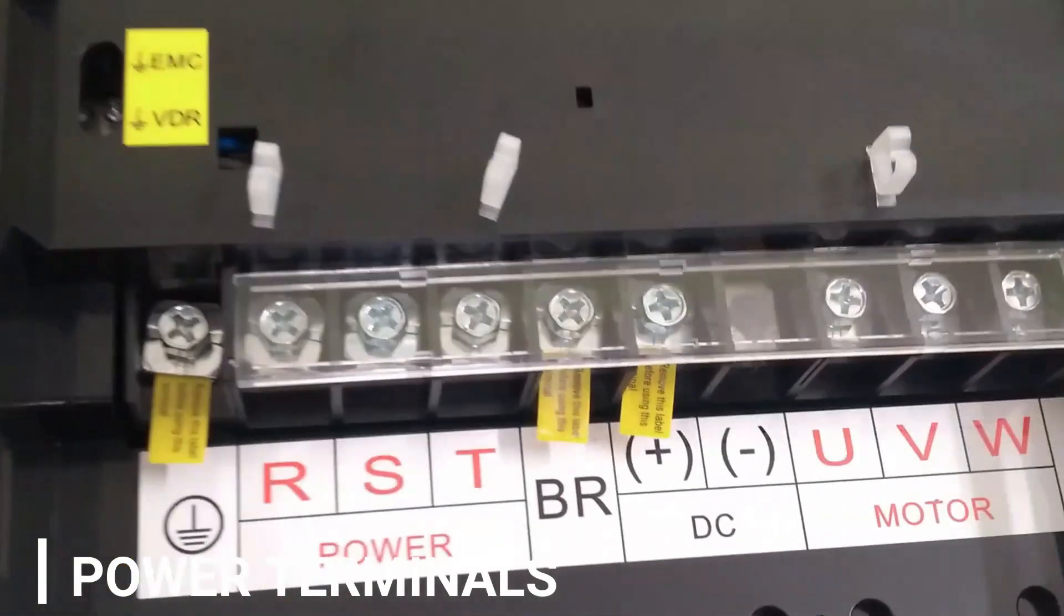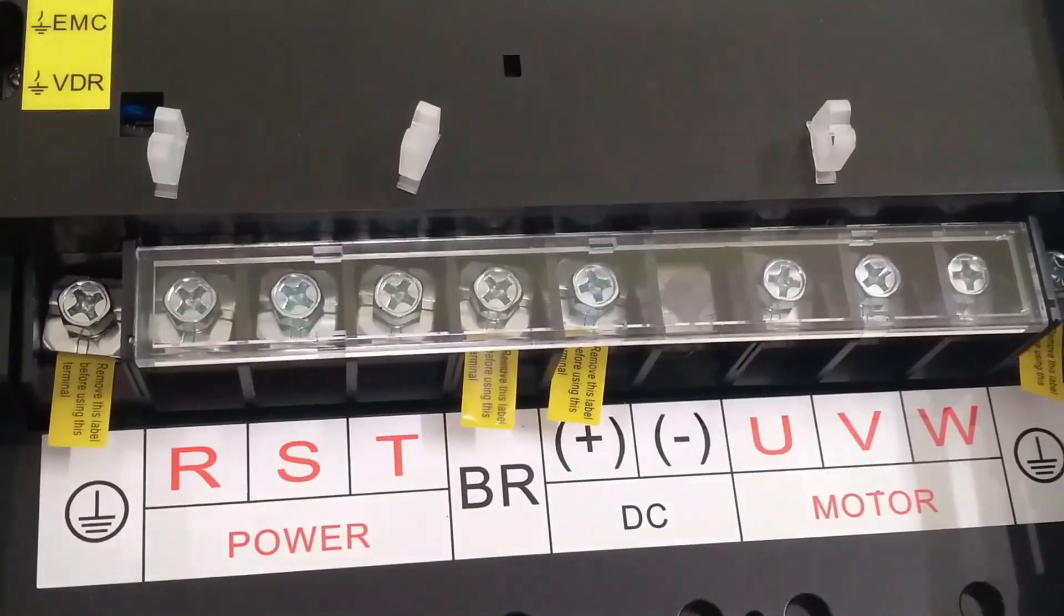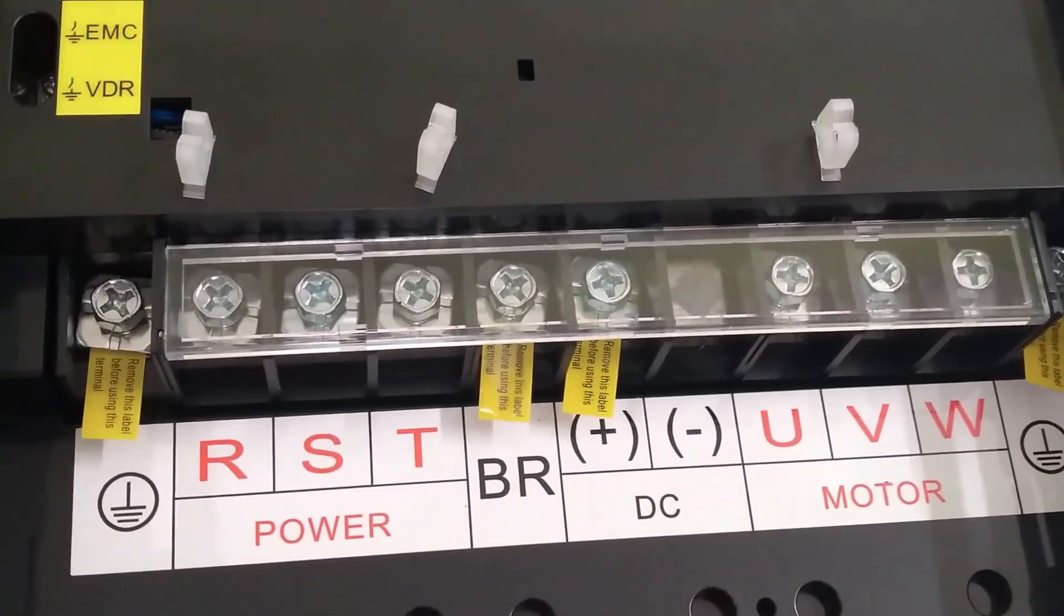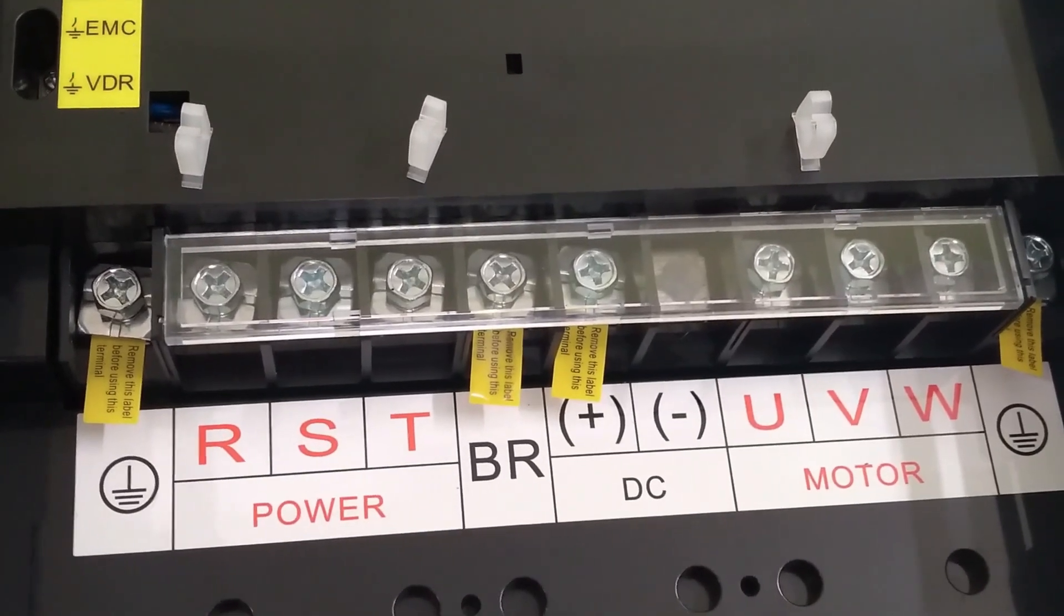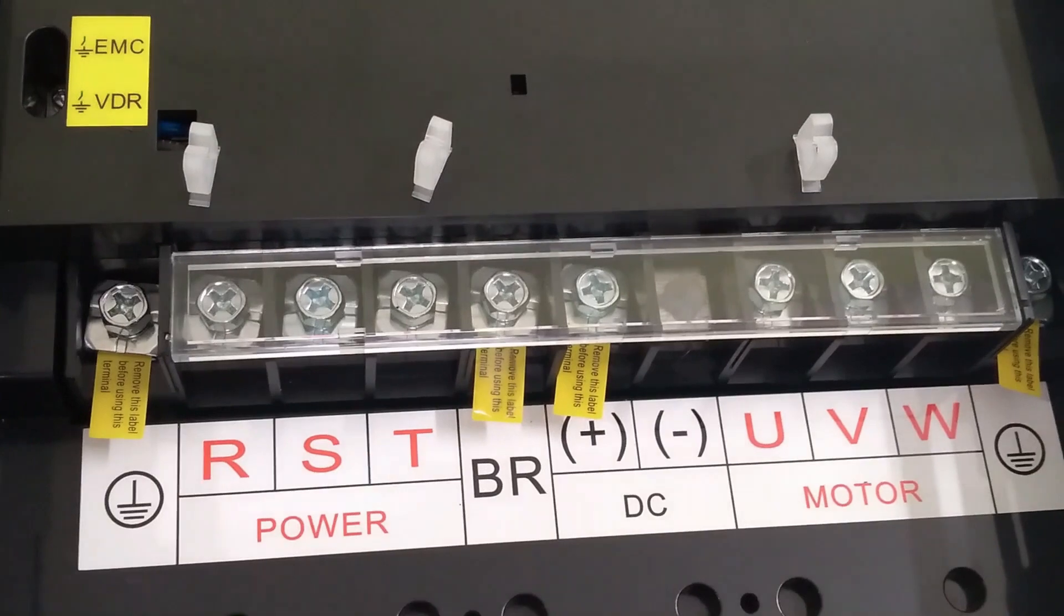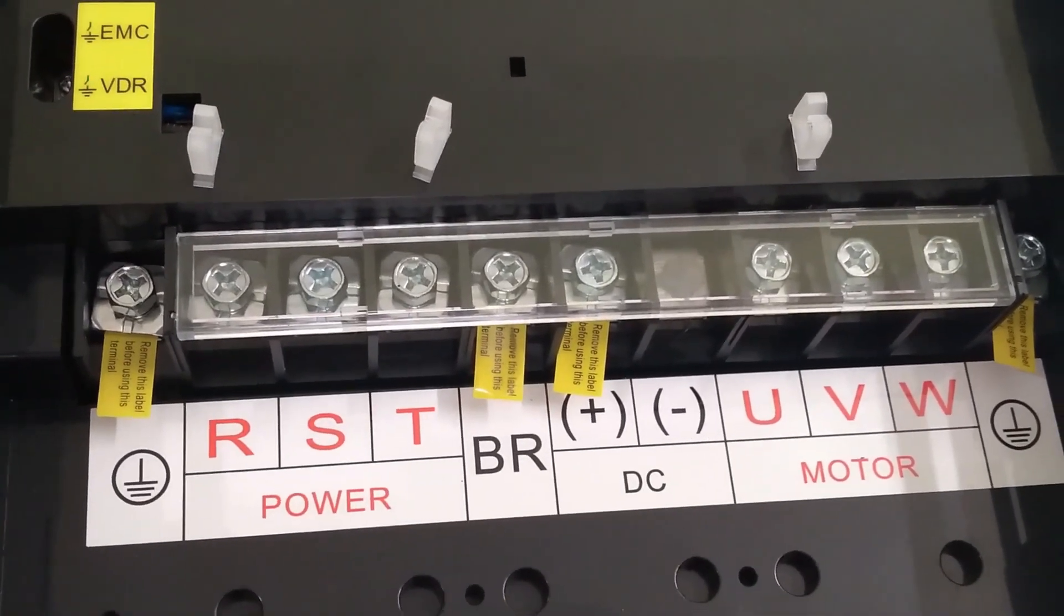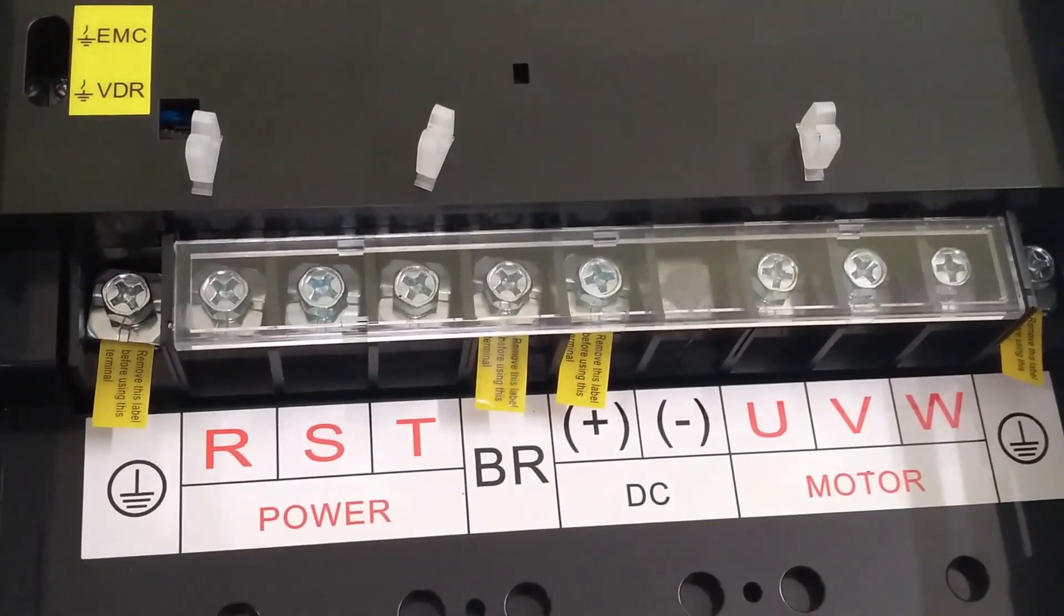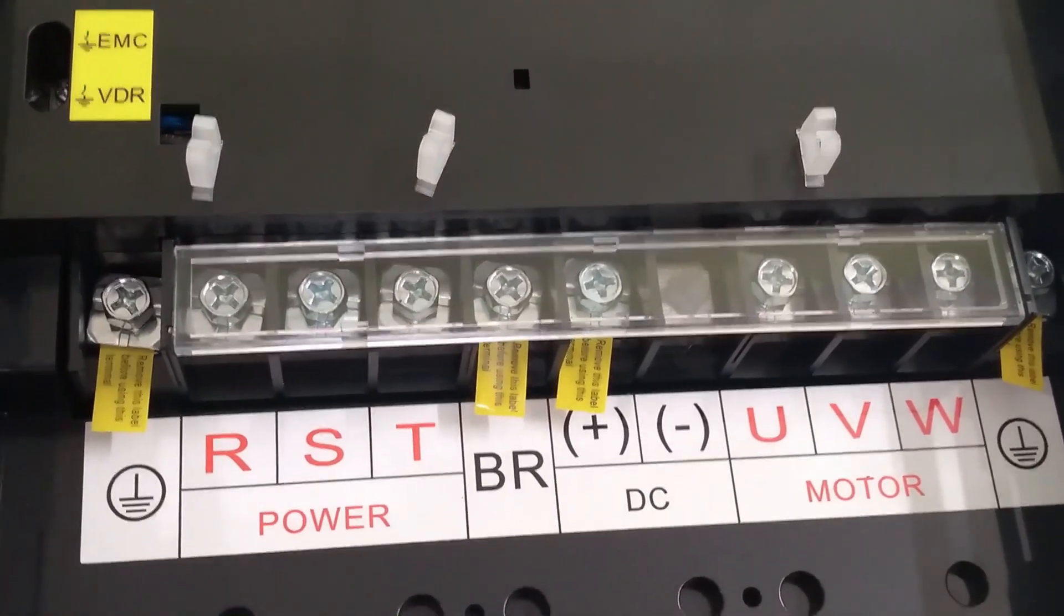At the left most, we have RST terminals for connecting main supply R, Y, B phase. Then we have positive and negative terminals of DC bus voltage. BR terminal is for connecting external braking resistor. Braking resistor is connected between BR terminal and DC positive terminal.